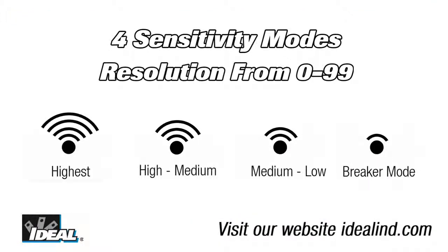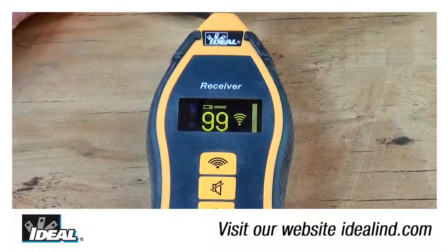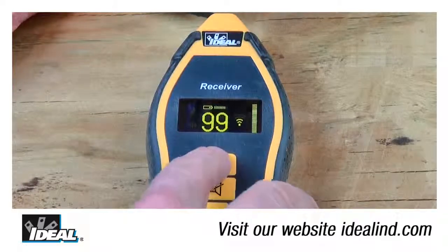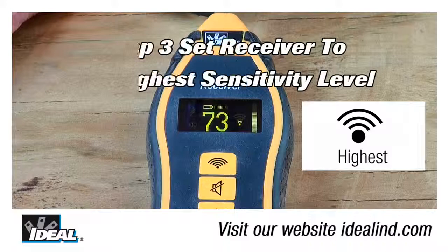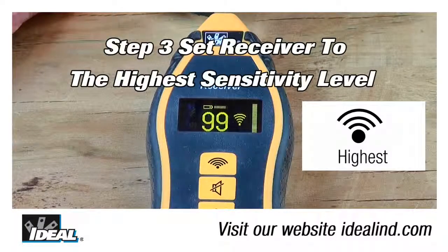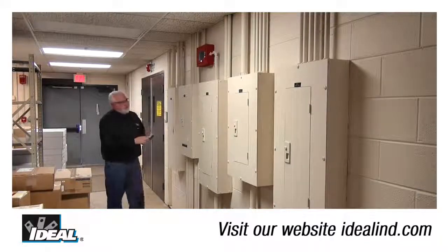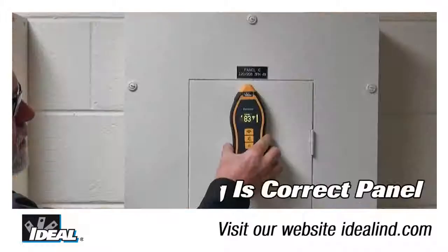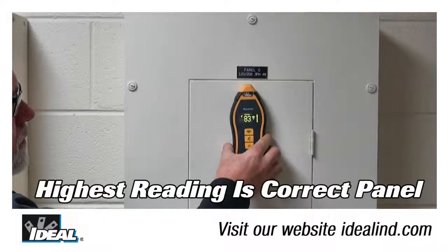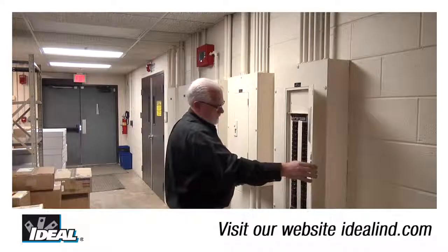The receiver has 4 sensitivity modes with great resolution from 0 to 99. The 4 sensitivity modes can help you identify the correct panel when more than one is present, and then select the breaker mode for breaker identification. Step 3 is to set the sensitivity to the highest sensitivity level to find the panel the breaker is in. Then place the receiver flat on the front cover near the top of each panel in the group of panels, looking for the panel with the highest reading. The panel with the highest reading is the correct panel.